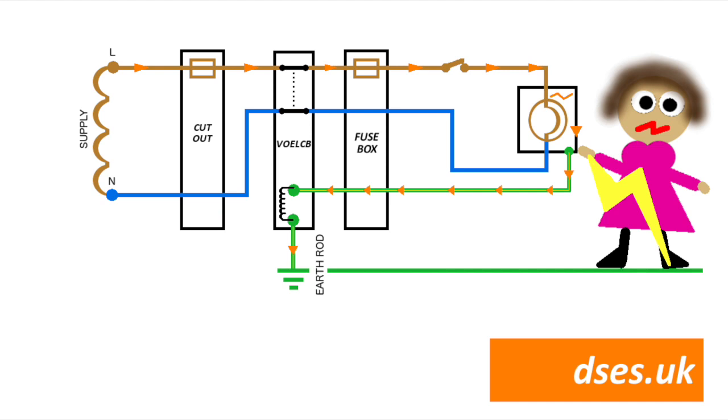In this scenario, we can't actually rely on the voltage operated earth leakage circuit breaker to actuate in a timely enough fashion, if indeed at all. The fault current may be enough to blow the fuse, but that's there to protect the wiring, not poor Doris, who's now got a potential difference right across her. For a safety device that is there to protect you from shock, it's not doing its job.